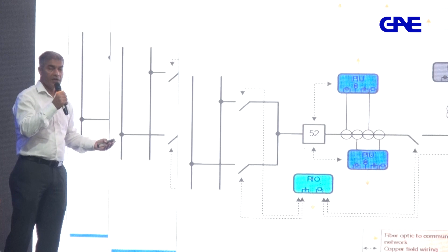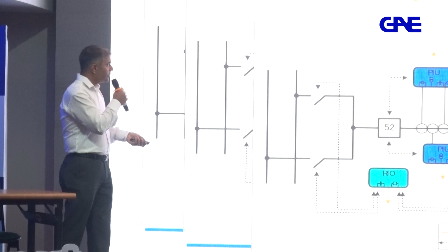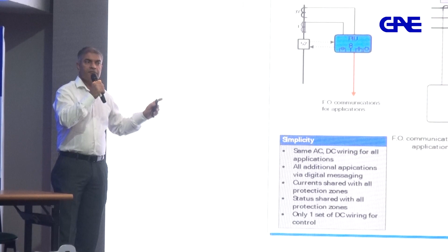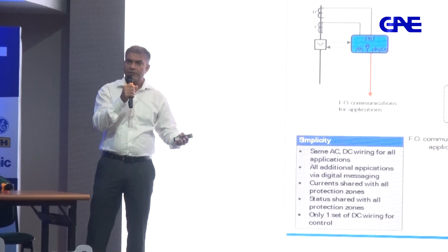So it's really your choice what type of wiring you want to pick, but you pick one architecture for wiring, and then wire every identical device the same way, right? So once you have decided that this is what I want to do, I want to use the process interface unit, repeat that for each bay, each identical device. So that means your wiring is standardized. When you produce your outdoor panel, every outdoor panel can be the same, because you know that you are using this process interface unit to connect to the circuit breaker, and all the wiring, all the references could be the same, okay? For every identical bay, your scheme is the same, your wiring is the same.